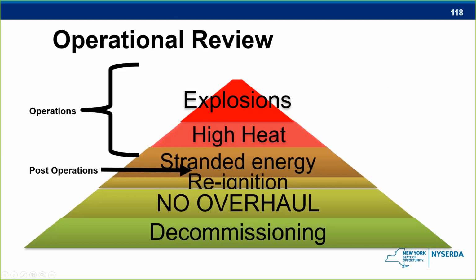All right, just to kind of review, for the operational people, this pyramid here, the explosions are our number one concern. We do not have any personal protective equipment to actually protect us against any type of explosion during an operation phase or any phase at all. But also we need to be concerned about the high heat. These things have a very high heat release rate. So if you're using water or some sort of hose line on it, you're going to have to use a lot of water to absorb the amount of heat. And keep that in mind when we don't want it to propagate to the cabinet next to it. We'll have the stranded energy that's going to be involved not only in the operational stage, but also in the post-operation stage. The reignition is very, very real during the post-operations. And also, we do not want firefighters doing any type of overhauling. There's no reason for us to look for pockets of fire in this thing. Leave it be. Decommissioning is also going to be part of that post-fire event. Next.